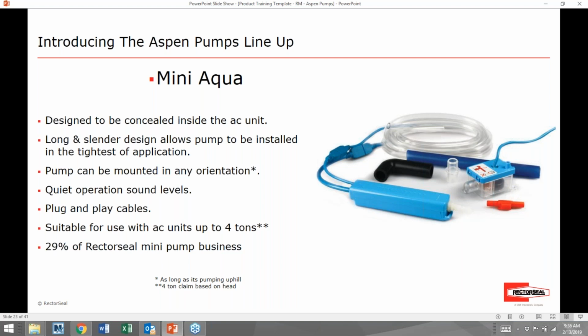Now, the pump is directional. There's an inlet side and a discharge side, and there are arrows marking that on the pump. This pump can be installed in any orientation as long as the discharge side of the pump is level or pointing upward. So again, people ask me all the time, is it orientation specific? Not as long as it's pumping flat or uphill is the quick answer.